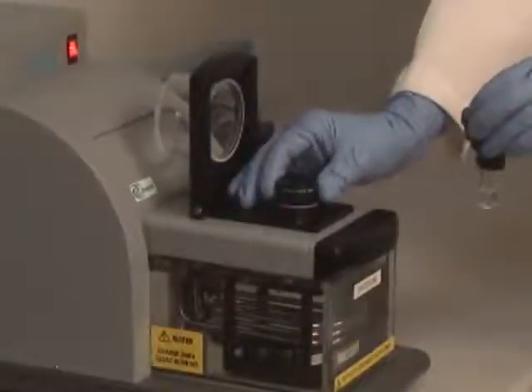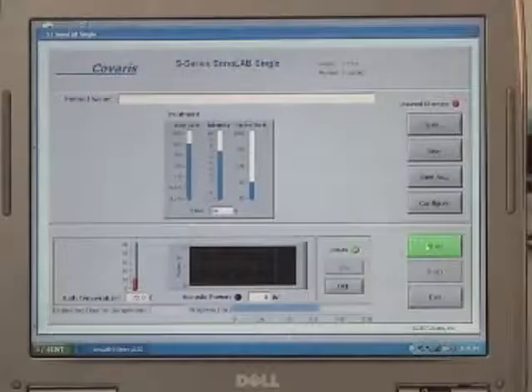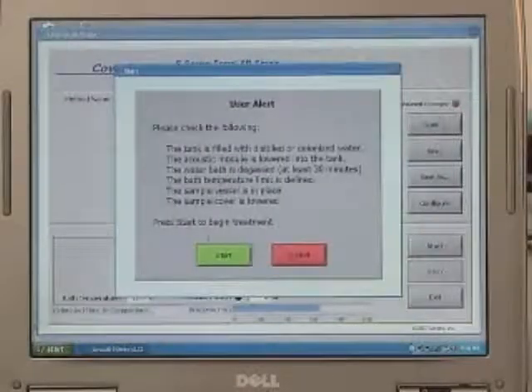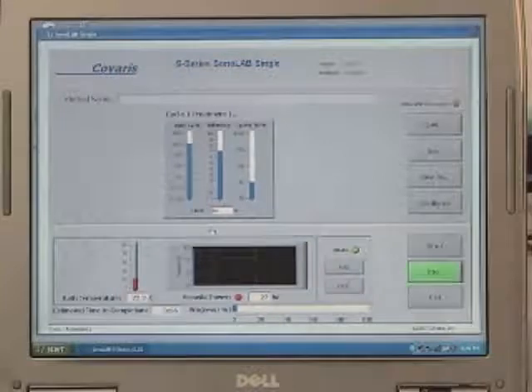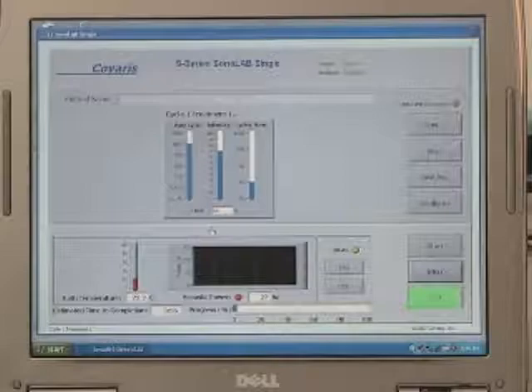Lift the cover and load in the sample tube. You are now ready to run a method. After selecting Start, a checklist dialog box opens to remind the operator of some key points for the successful operation. Next, select Start. Stop stops the method at any time, and Exit shuts down the SonoLab single program.